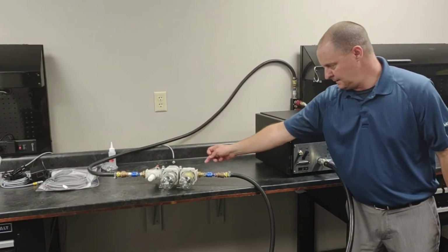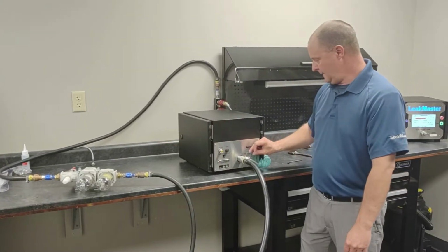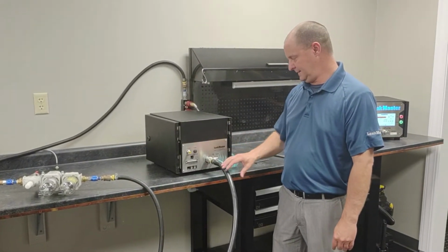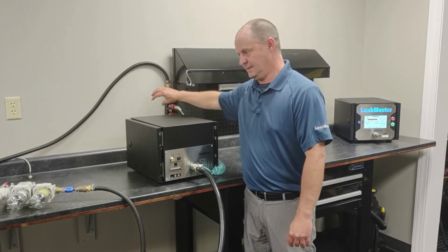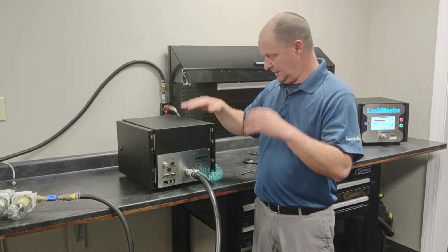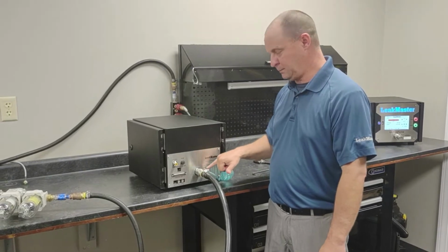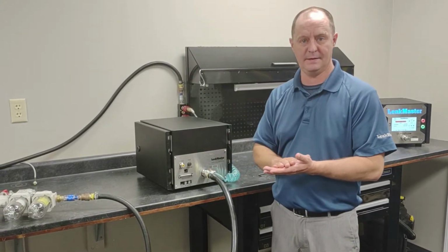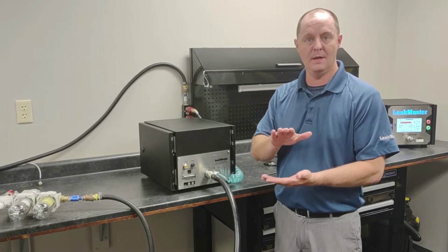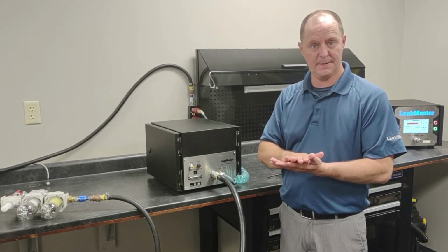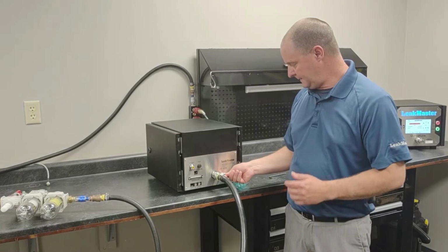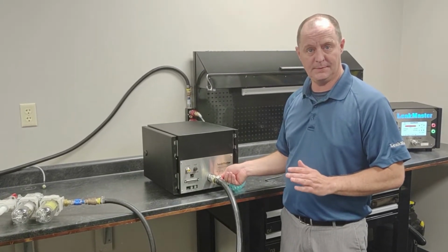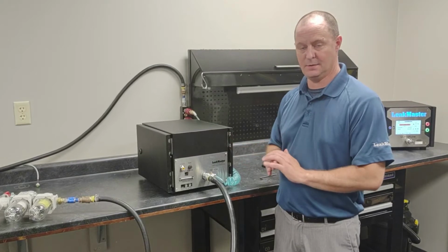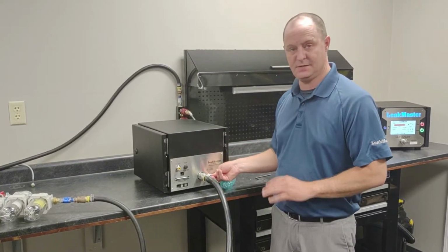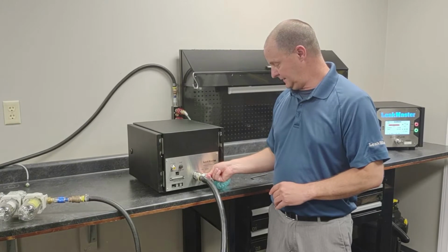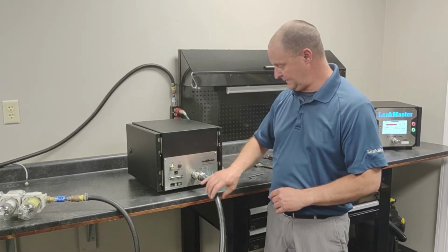Now, if you teed off right here, then you've got clean, dry air. But the purpose of having them separated is if you have large gross leaks at the front end here, say you had a huge leak, you can cause a pressure drop here, and we don't want a pressure drop to occur here because that can affect the function of our valves. If it drops too low, the internal pilot valves won't shift properly. So we want to make sure that we have 80 psi on this at all times. It's regulated down inside with its own precision regulator, so you don't have to worry about that. Just make sure there's sufficient air pressure to this, and it's separated from the air in source.